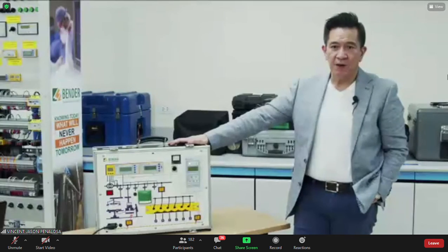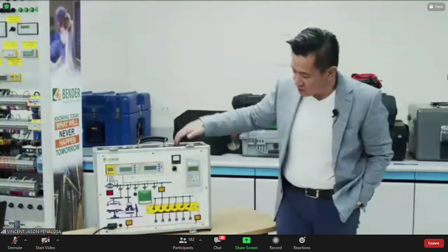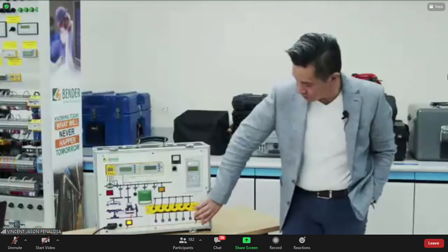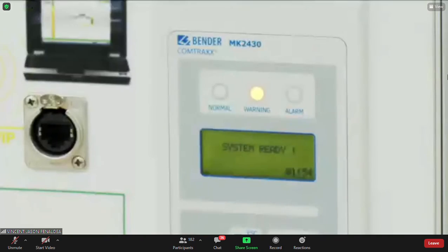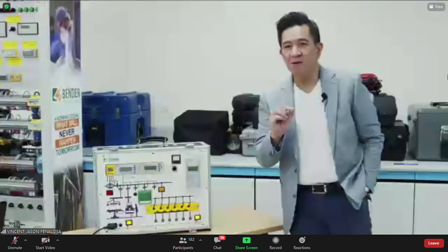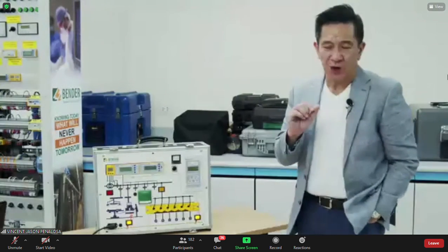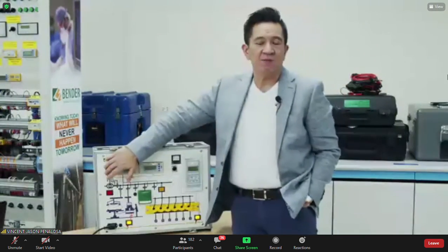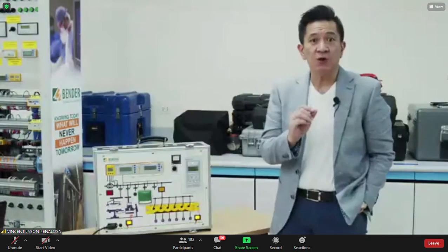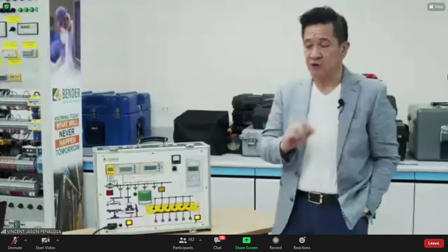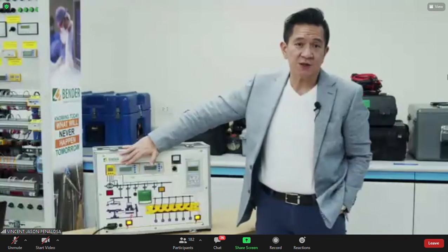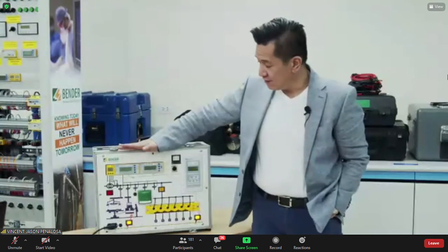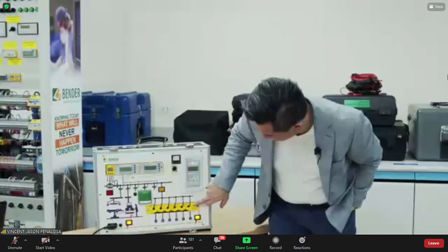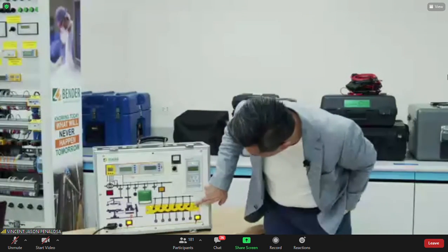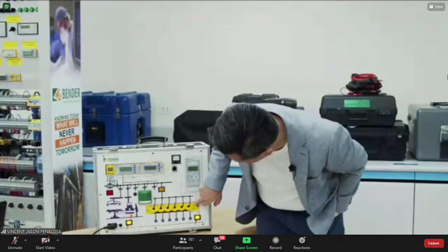So what will I do now? What I will do now is actually create some other faults. So let's see. Remember, we're talking 1 milliamp fault location, right? 1 milliamp fault location. The insulation monitoring device already determined that I have an insulation fault. It's the fault locator's turn to actually find it. So right now, it's telling me that chances are I have a fault somewhere on channel 1.